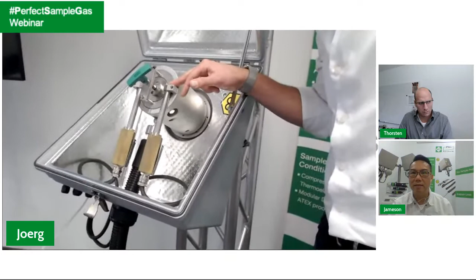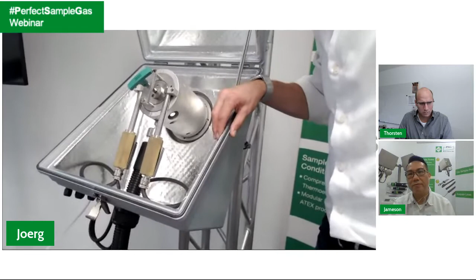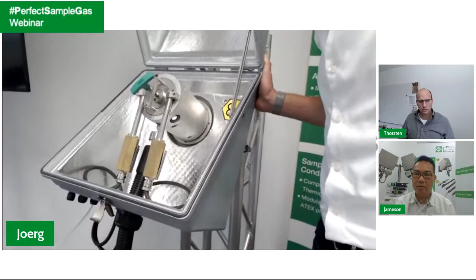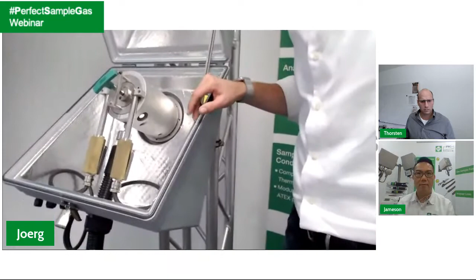Jameson, you just mentioned the acid dew point. Depending on the gas components and the mixture of gas components, there could be a very high acid dew point, and it may even be necessary for the heating to go higher than 150 degrees C. If we need only 150 degrees C, we can leave away one heating cartridge, so then we are good with just one. But if we need to reach 180 degrees C, this is the solution.